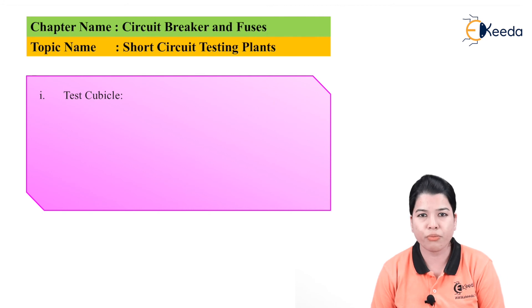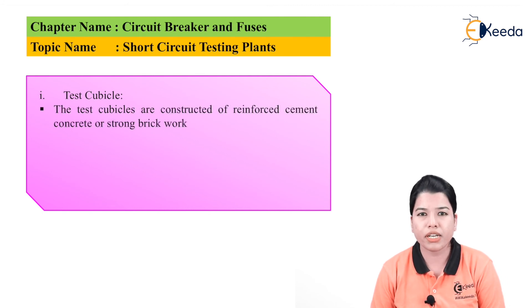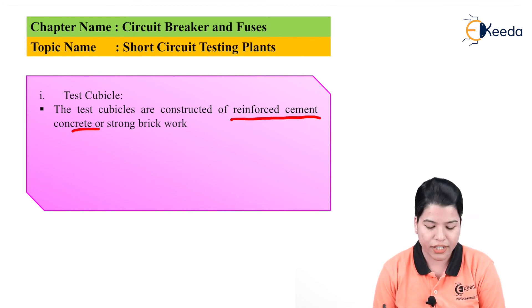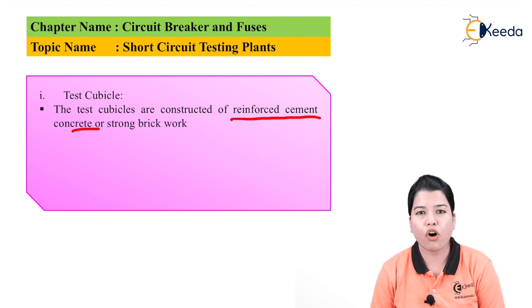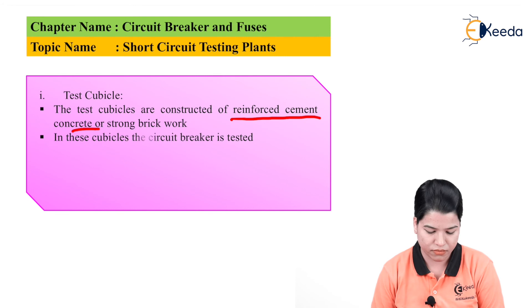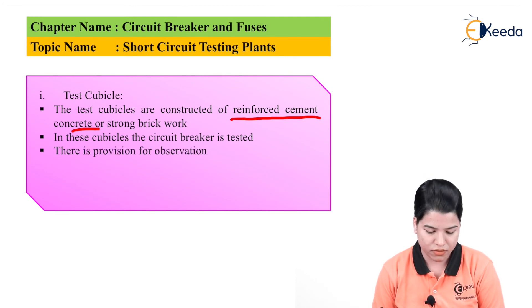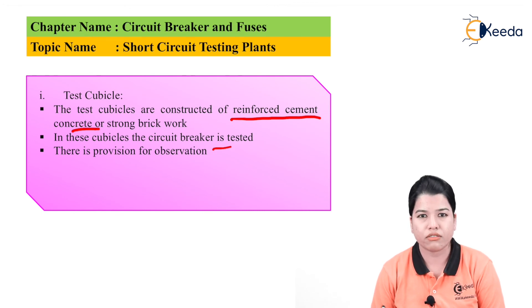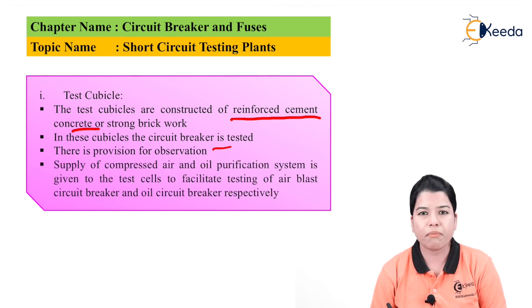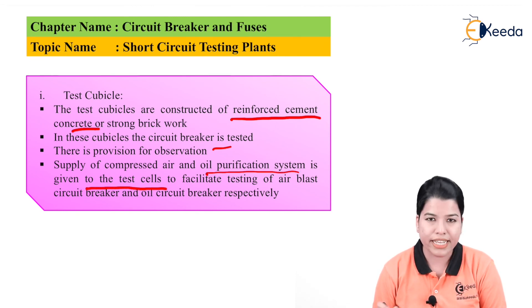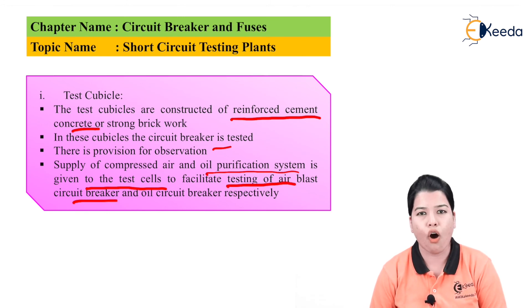The test cubicle is constructed of reinforced cement, concrete, or strong brickwork, and the test circuit breaker is placed inside it. A provision for observation is made, and supply of compressed air and an oil purification system is provided to the test cell to facilitate testing of air-blast or oil circuit breakers.